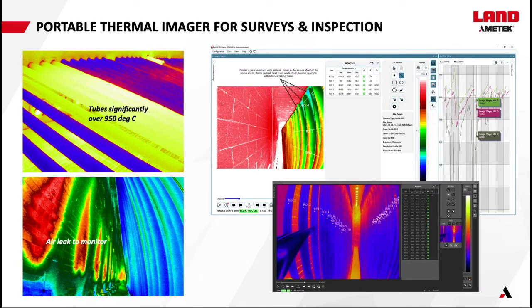This slide shows some interesting frames that we captured during some recent surveys. So you can see in the top left-hand side, there are some tubes significantly over 950 degrees C. Again, those would have looked hot to a Cyclops operator, so the operator carrying around the portable instrument may have spotted those hot temperatures, but he may not have spotted the very significantly elevated temperatures where that maximum heat flux is. And we saw that with the thermal imager, but that was over 950 degrees C, obviously very concerning to that end user. On the bottom left-hand side, on a terrace wall reformer, we saw some air leaks around the burner tiles, some pretty significant ones.